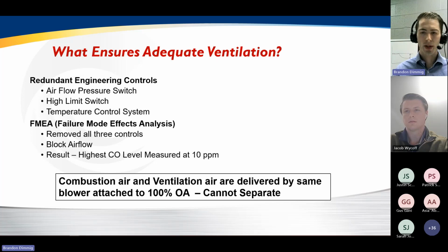But a key point is that the ventilation air and combustion air are one and the same. You cannot separate them. So if you don't have proper ventilation, if you don't have outside air, you don't have combustion.